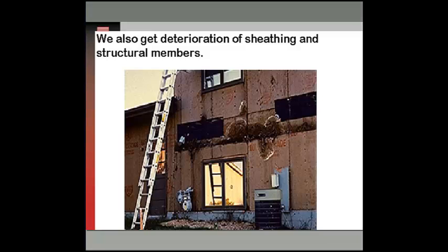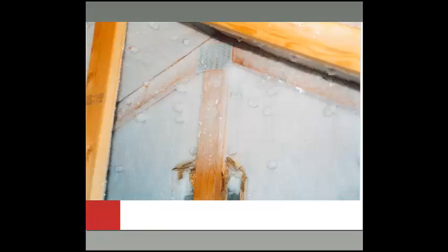So they were pressurizing that ceiling cavity, and there was no air barrier material. They had just stuffed air permeable insulation into that band joist area, and over the course of 10 or 15 years, the condensation was just rotting out the band joist. So you can have hidden durability issues. This building got skinned thinking it was a window infiltration, a window leak issue, and when they got it skinned like that, they saw something else major was going on with the building. So duct leakage in certain climates can have durability issues.